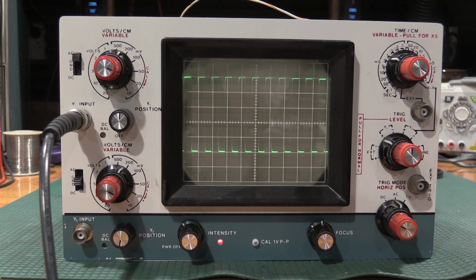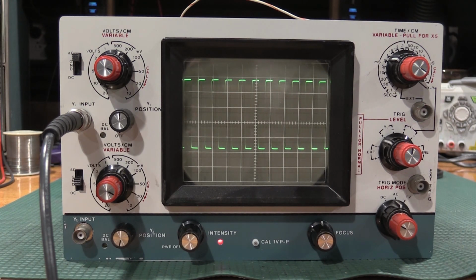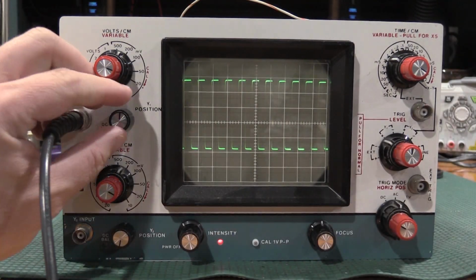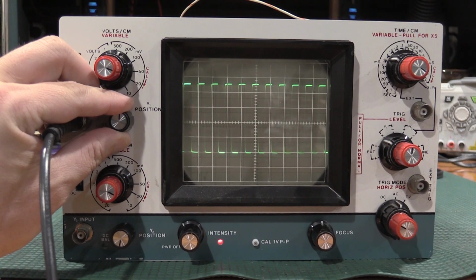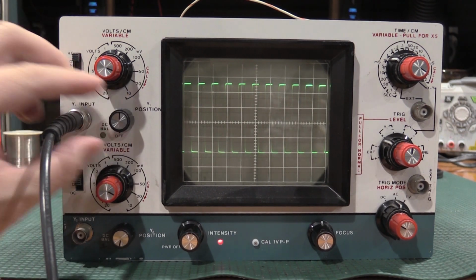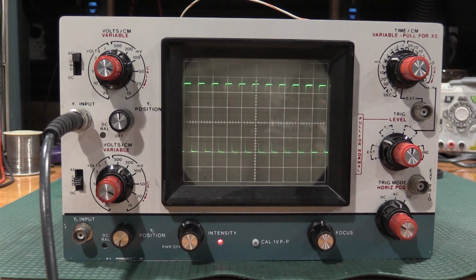And I have the calibration generator dialed in, but it's telling me that the error on the scope is right at the borderline, so probably 7.85% low. Because if I turn it into 1 volt standard here, we can see it decreases just a little bit. So we will need to give it a little bit more gas on the vertical amplifier, which is fine. Now I have the camera set directly square on, so you guys are going to have a better view than I will. I'm actually using the camera as a magnifying glass to look at the scope dead on. The neat part about that is it's very easy for me to see what you guys see.